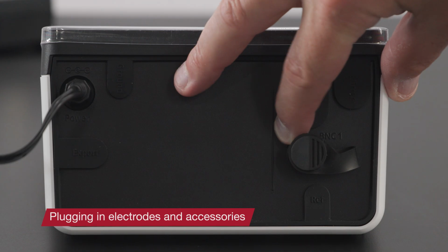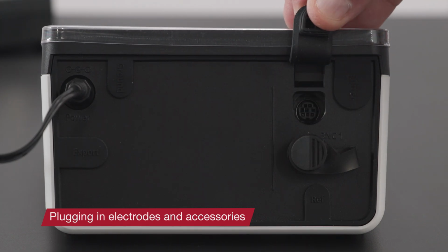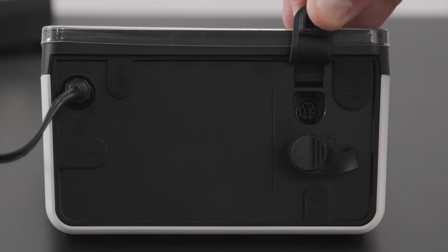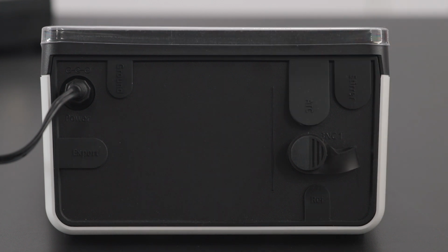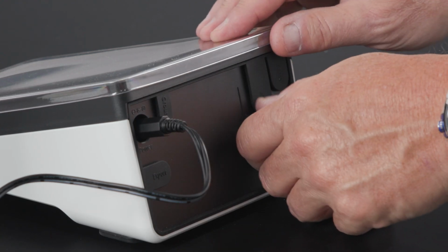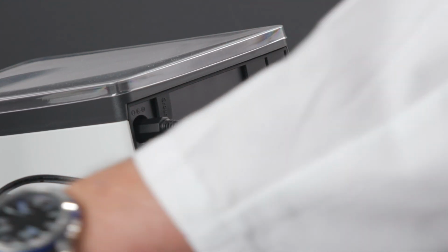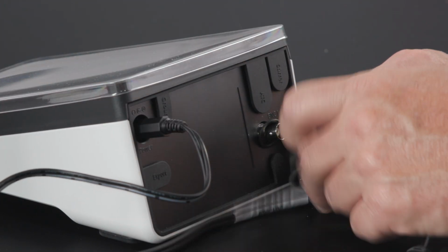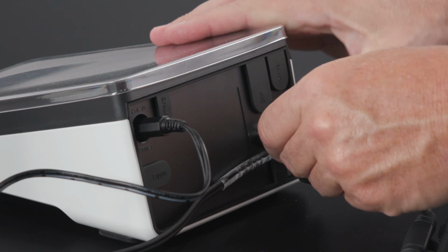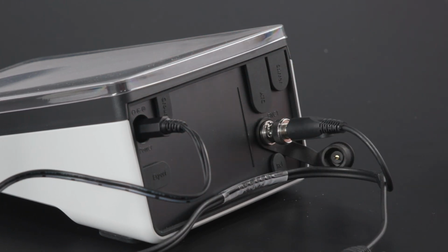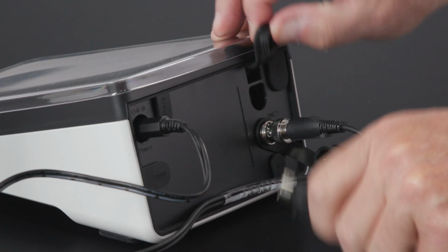Inputs for electrodes and accessories are located on the back of the Orion ProStar meter. Each has a protective cap to keep out dust and water. Leave these caps in place unless the input is being used. Connect the pH electrode by lifting the cap from the BNC input and inserting the connector fully into the input, then twist to lock it in place. The shorting cap can be used to troubleshoot the meter, so retain it for later use.